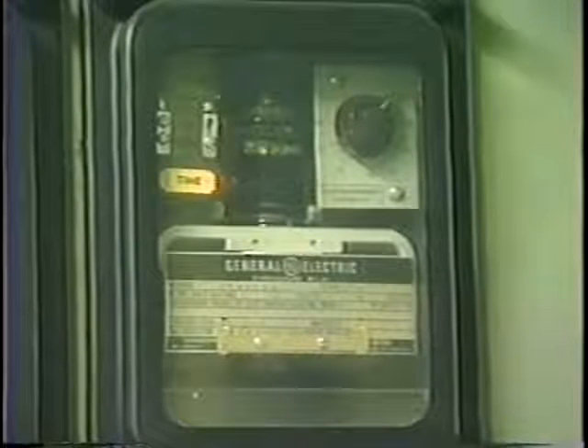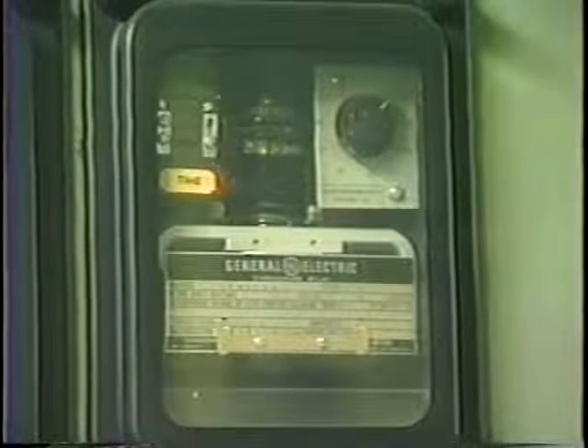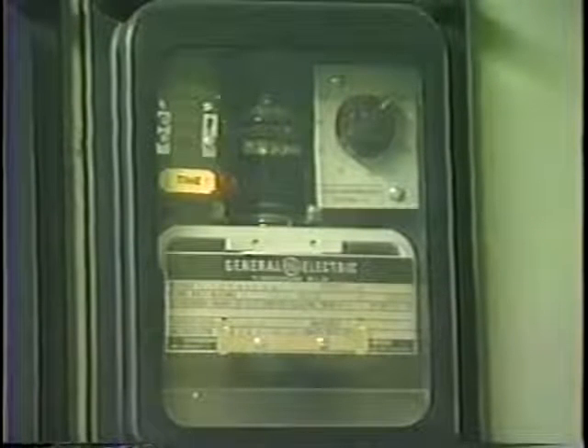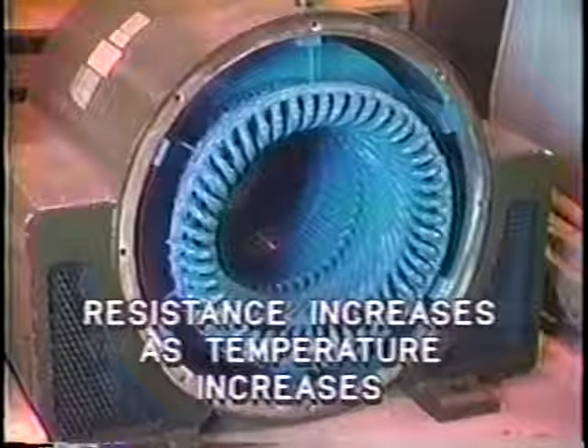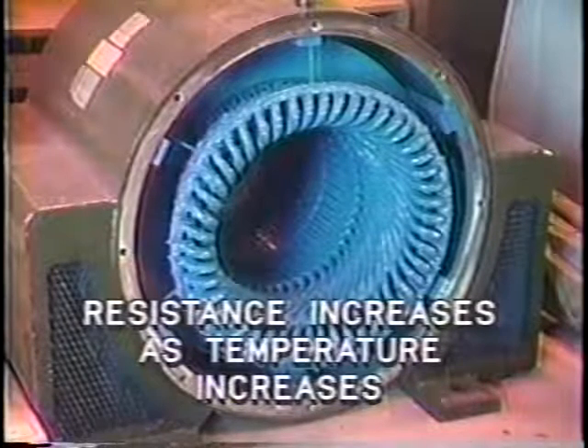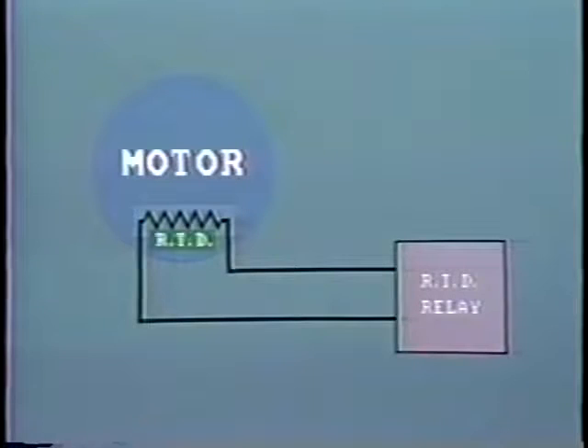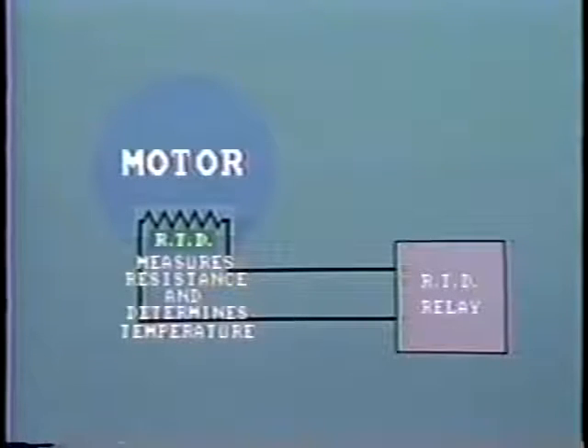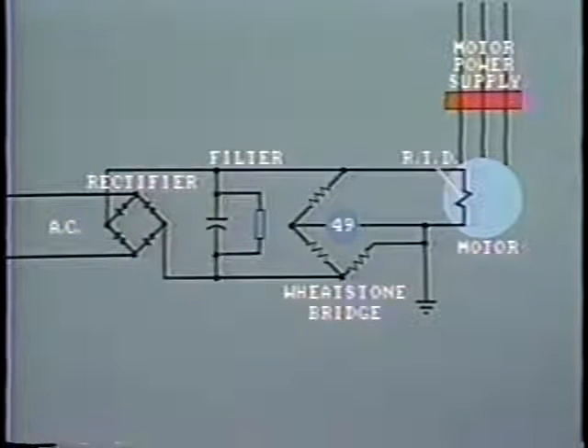These RTDs, also known as search coils, are connected to a temperature relay which measures the resistance of the detector. As we know, the resistance of any conductor increases as temperature increases. The detector is made of material which has a linear change in resistance as temperature changes. So by measuring the value of resistance, the relay can accurately determine the temperature inside the motor. When the temperature exceeds a specified limit, the relay operates and de-energizes the motor. This schematic shows how it works.